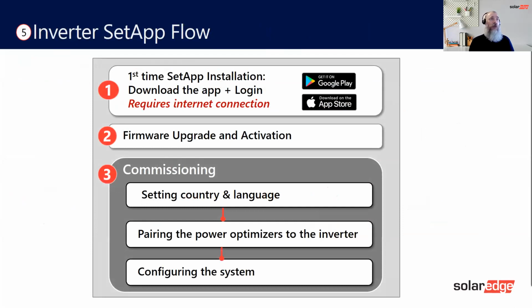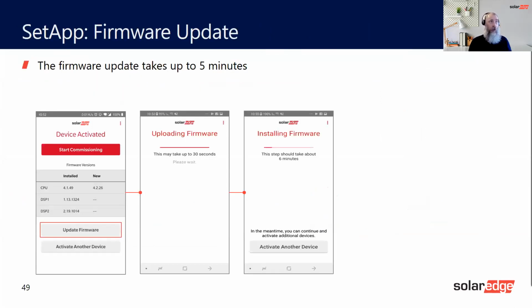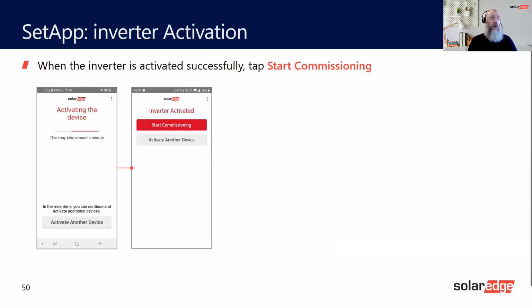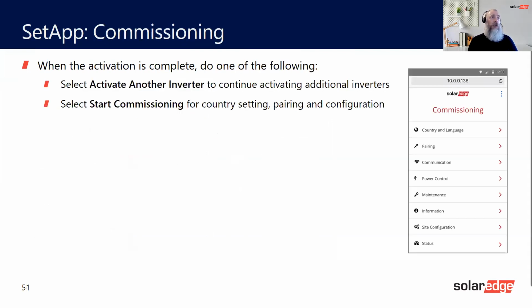Again, using SetApp, which you're familiar with, so we won't dwell on these too long. This is what I was saying about the firmware installing, depending on how long the inverter's been away from manufacturing. So if it's been 6 months, you may have a couple of updates to do. If it's pretty much as we expect all our products to be, a very short time between manufacturing and installation, the firmware difference shouldn't be that great. So commissioning is the same as any other. Once you've done it, you set the language and the grid settings. And then you carry on as normal.